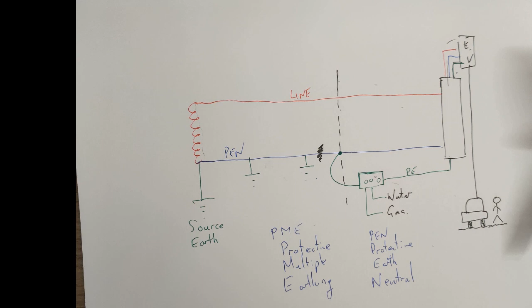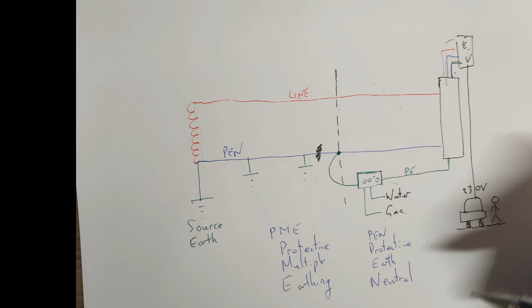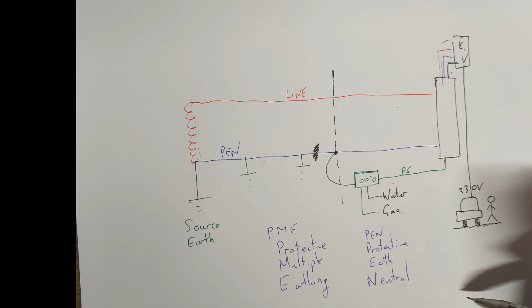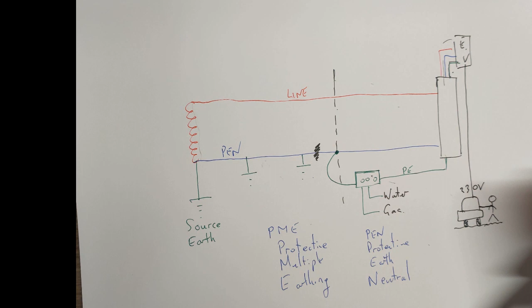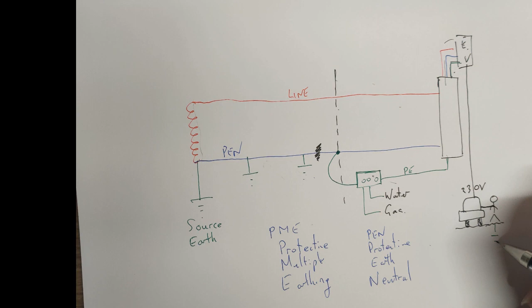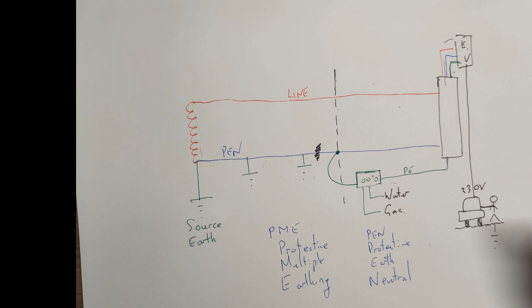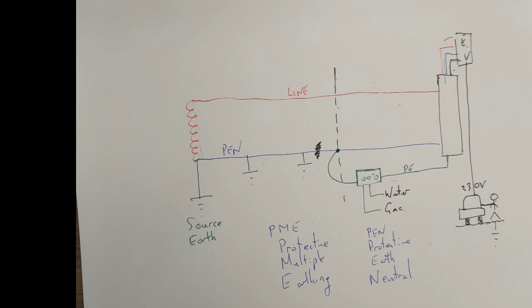charger, and your car is now at 230 volts. Now that's not a problem because it's got rubber tyres, so it's insulated from the ground until such time that Tim comes along and touches that car. He is now part of the earthing arrangement, and 230 volts is going through him, and it's bye-bye Tim. That is why, if these EV charging units are put in the wrong way, they are lethal.